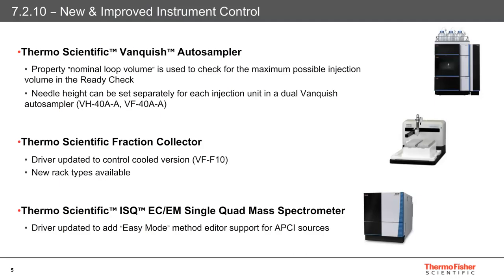Finally, for Thermo Scientific instruments, there's an update to the ISQ EM driver that simplifies the process for setting parameters relating to the optional APCI source. The Easy Mode, which is accessed from the Chromeleon CDS Method Editor, can calculate all the relevant settings based on the pump flow value.